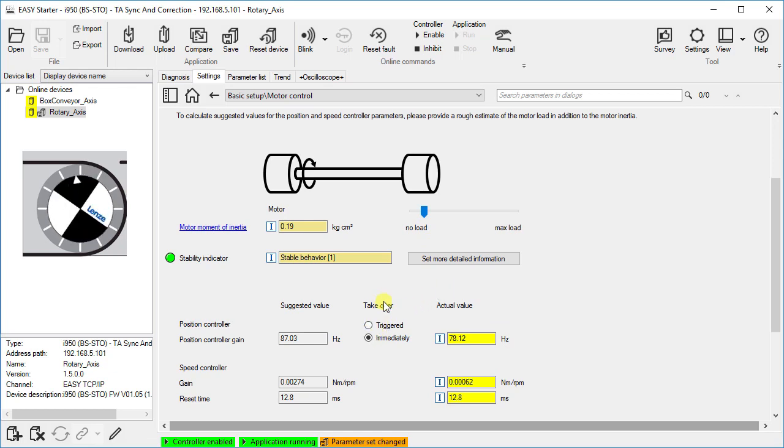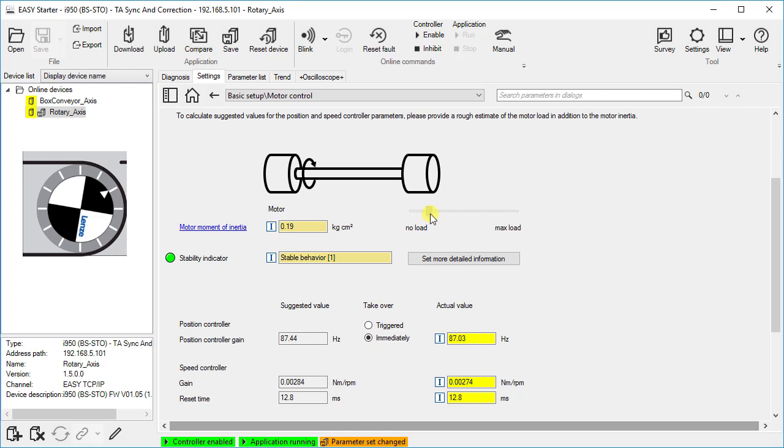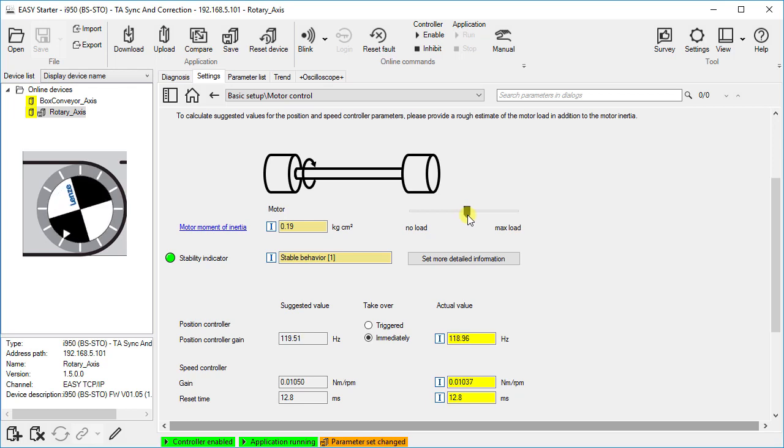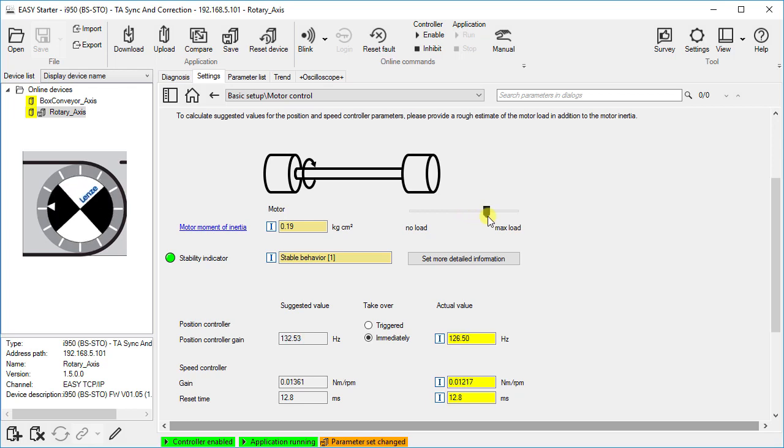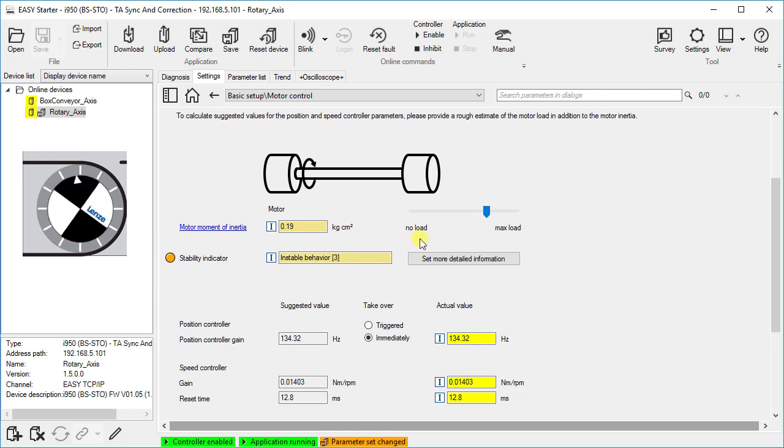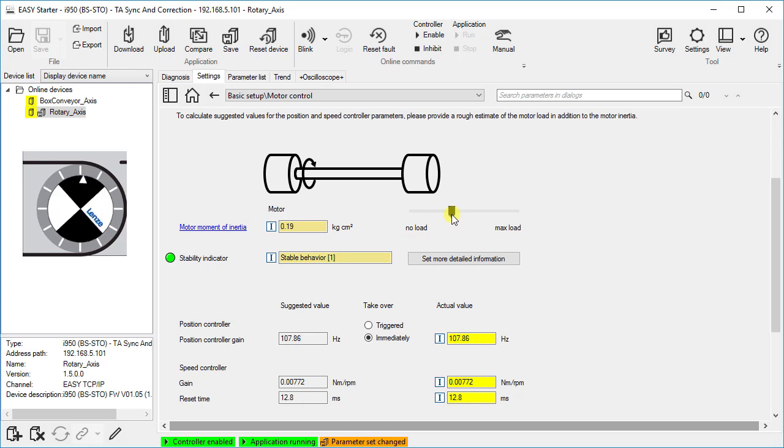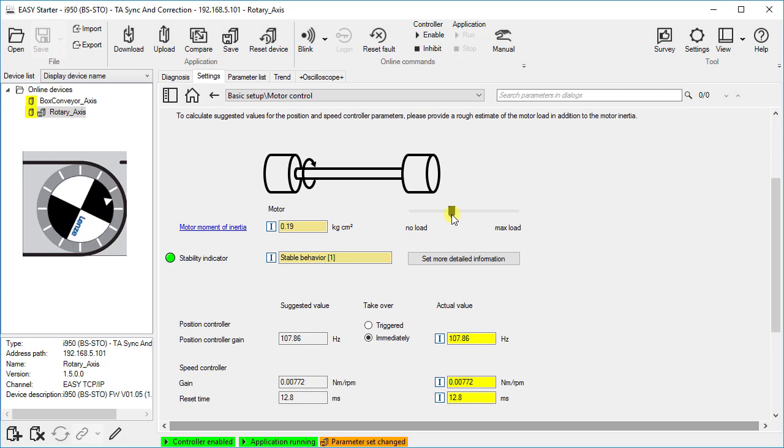Let us switch to immediate takeover and move the slider further to the right. The suggested values are now activated without confirmation. Moving the slider further to the right, we reach the stability limit. In the stability indicator the unstable state is shown immediately. We move the slider back approximately to the half distance and get the optimal settings for a stable and dynamic operation.